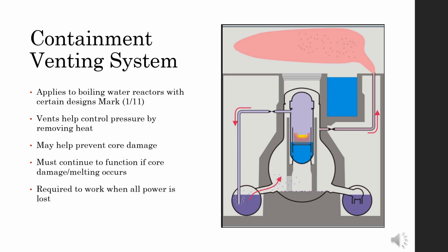Containment venting systems apply to boiling water reactors with certain designs, marks 1 and 2. The main concern is pressure control and removing heat to prevent core damage, since core damage is ultimately how fission products get outside the ship or outside the plant. So the requirement is that even when all power is lost, you still have a containment venting system in place.